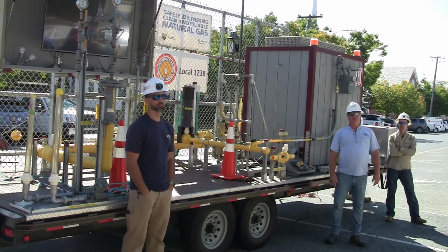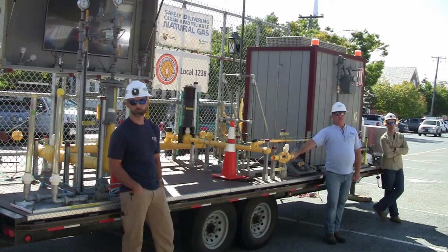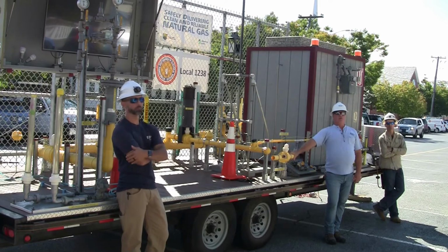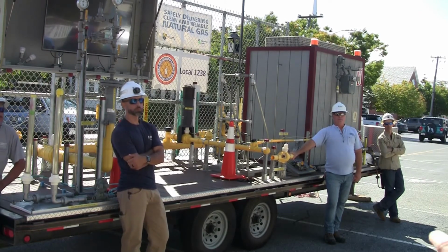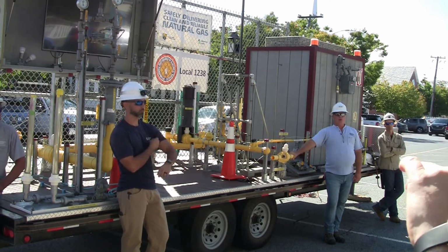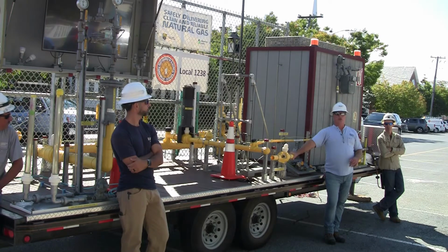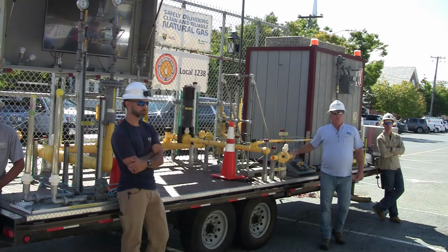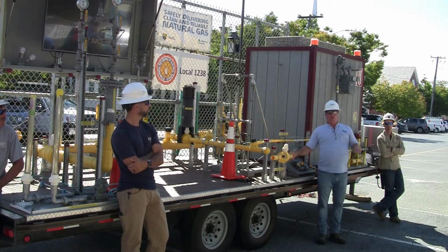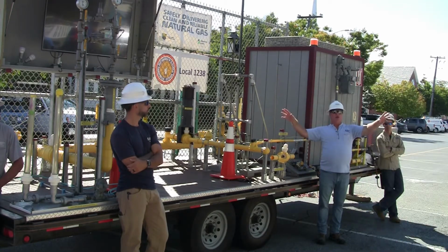I had a question about that Friday special. They hit that 8-inch main, and the whole time it was just blowing. Yeah, it blew for about 50 minutes. Did you guys call in emergency tickets to dig down and squeeze the pipe? Emergencies are automatically called once damage is reported. I meant the miss utility emergency ticket. Yeah, once we hear that damage is done, it's automatically called. How far away from that break did you dig? We usually go 100 feet in each direction, just to cover our boundary. Gotcha.